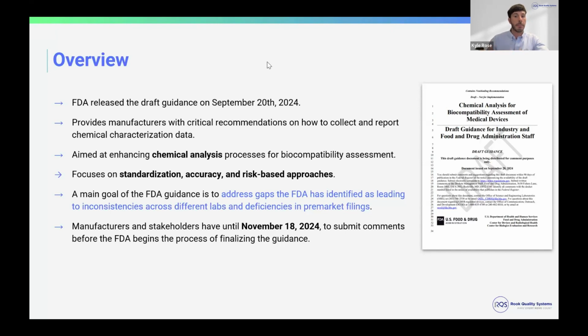So for those of you that might be new or not completely understand what this is, you have your typical biocompatibility assessment for your device. This is typically for devices that contact the body or implanted devices. There's also the chemical analysis, which is if there's chemicals leaching off of your device or that are part of the material that might come off during heating or any other use of the device. The FDA wants to identify these chemicals and also analyze any hazards from these chemicals, any biocompatibility risks, things like that. So that's the main focus of this chemical analysis for biocompatibility.